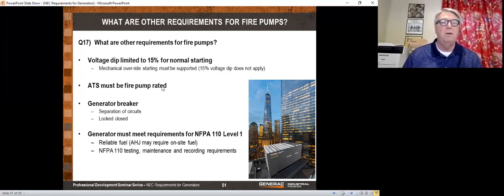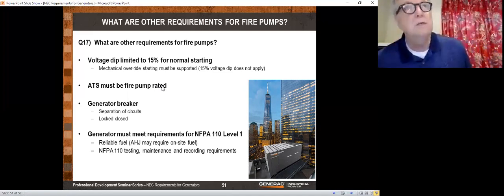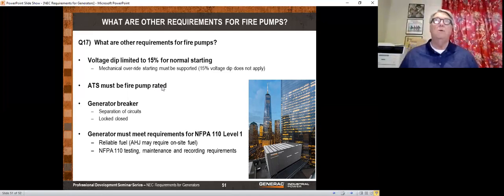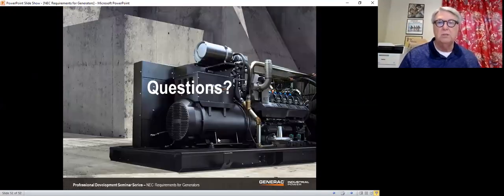The ATS must be fire pump rated. The ATS is always supplied by the fire pump manufacturer, not by the generator manufacturer. So for instance, at Portneuf Hospital up in Pocatello, they have 18 transfer switches. We supplied 17, and the fire pump manufacturer supplied 1. We don't even sell fire pump rated transfer switches. We could get them, but we'd have to go to a fire pump manufacturer and buy them. Generally they come as a package with the fire pump. The generator must meet the requirements of NFPA 110 Level 1. In other words, it's got to meet all the requirements for an emergency generator.